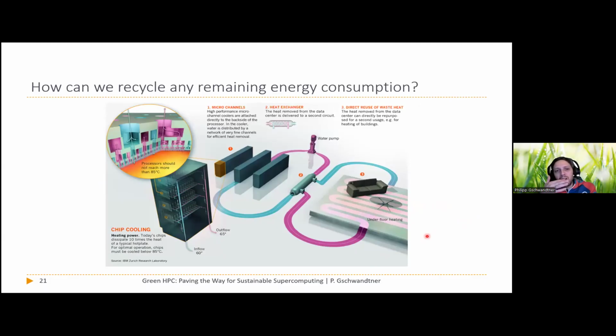Another thing we can do is recycle the heat produced by the system. Many data centers already do this, with an inflow temperature for the cooling water of 60 degrees, for example, and an outflow temperature of 65 degrees. That 65-degree water is hot enough to pump through a heat exchanger and heat office space. Many data centers are built next to lakes or rivers, getting a free supply of cool water to cool their systems.